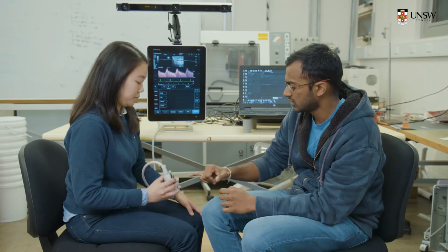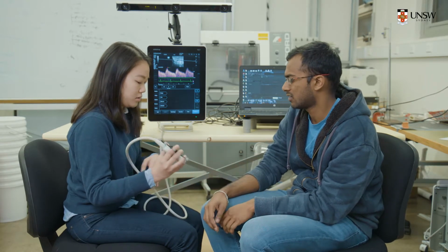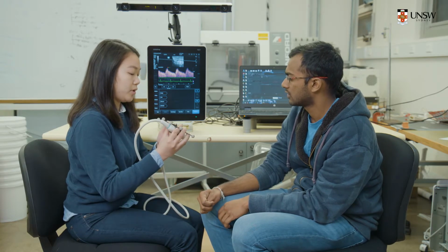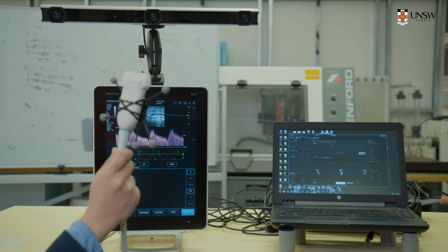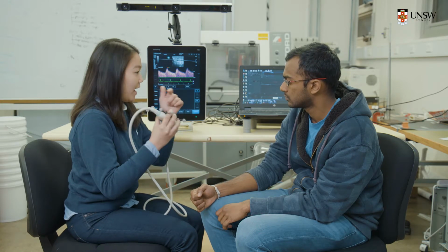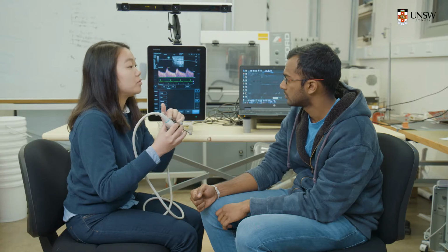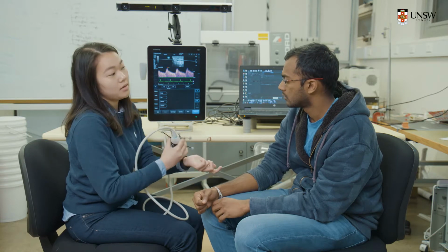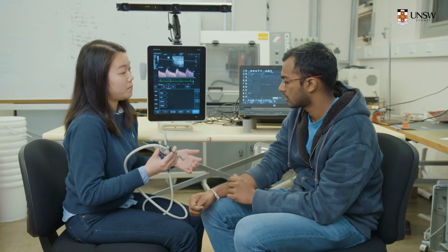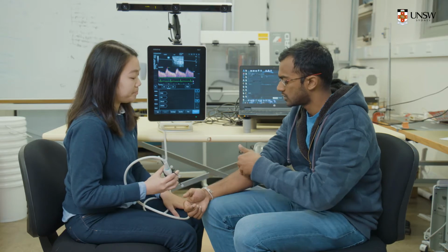You showed me this. You said something about the rigid body. What does that do? So if you look, the camera actually tracks the rigid body. That's how we locate the vessel of the patient. That's basically the idea of getting the camera to locate the rigid body, and that's how we locate the patient, because we scan the AVF and we can know the location. So when you're moving, the camera knows where the probe is. The camera will be able to track the probe.